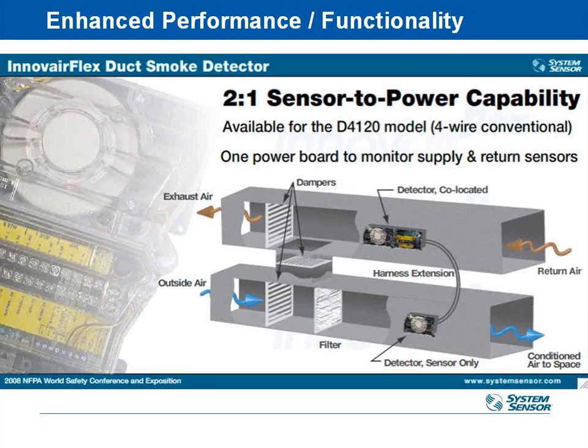And this just shows an example of what I'm talking about here. This shows a combined piece on the return duct with the detector and the control board, and then it shows a second detector head for the supply air. Both of them are wired together here, and then obviously just the return air one is wired back to the actual fan itself. So instead of wiring both of them back to the fan, you only have to wire one of them back to the fan, but you do have to wire them to each other. But it simplifies things, and it allows you to share accessories and stuff like that.